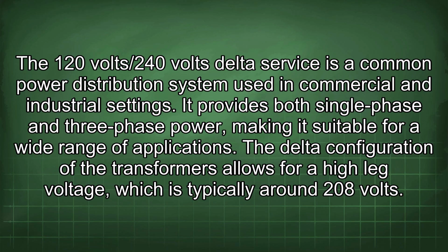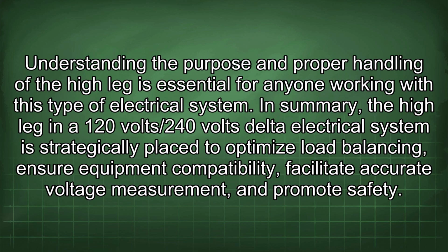The 120-volt/240-volt delta service is a common power distribution system used in commercial and industrial settings. It provides both single-phase and three-phase power, making it suitable for a wide range of applications. The delta configuration of the transformers allows for a high leg voltage, which is typically around 208 volts. Understanding the purpose and proper handling of the high leg is essential for anyone working with this type of electrical system.